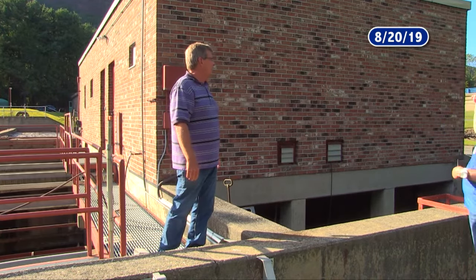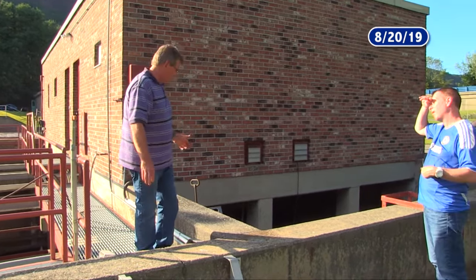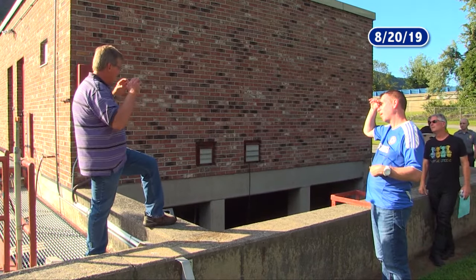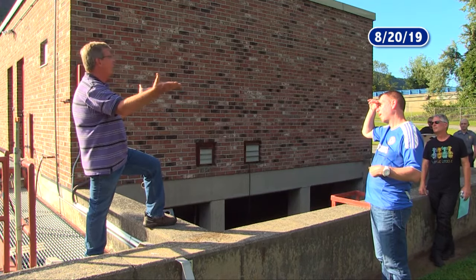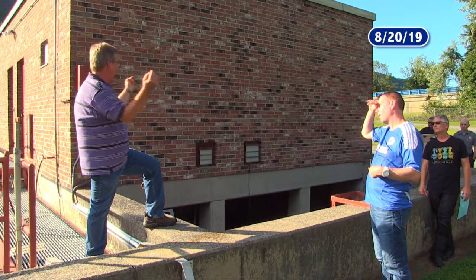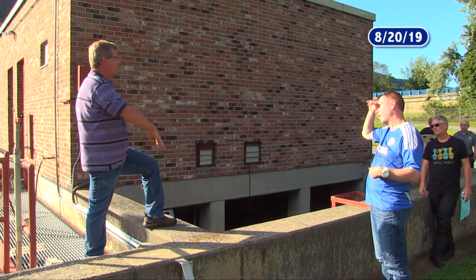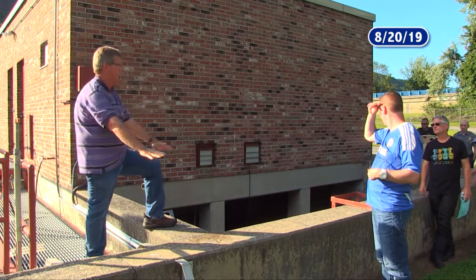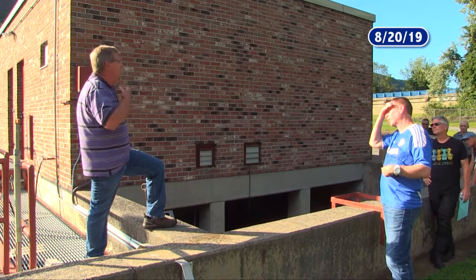And rainfall is the primary thing that causes you to have high flow? Yeah, rainfall. That's the primary thing for higher flow. Especially when it's been raining a lot regularly, like last year, and the water table comes up. Now, there's no place for that water to perk to, so it stays on the surface. And then it works into the collection system. It actually pushes through the cracks into the collection system and gets all the way up. Normally when it rains, the water perks down and goes past the collection system into the water table. And you get a little bit of a bump. If it's been dry for a really long time, that's what you see.